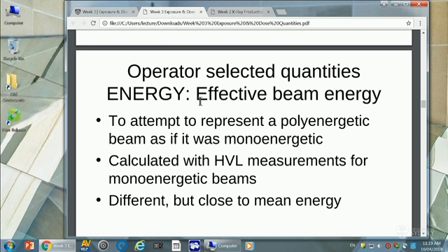If you were X-raying an abdomen, you set 70 kVp and 30 mAs, that's what you're going to set. Then you check the half value layer of that, and then you can say, well, I gave them the equivalent of 63 keV. And if you gave a different exposure, you'd re-look at it, because your half value layer would change if your energy has changed.